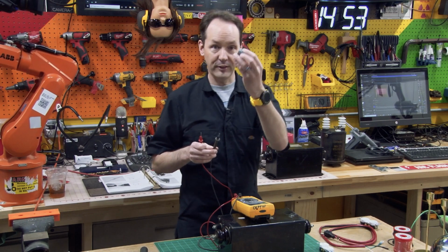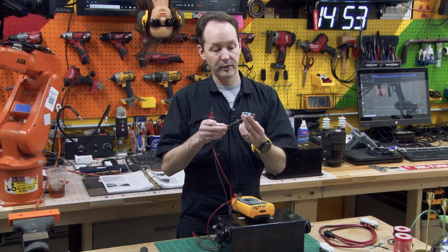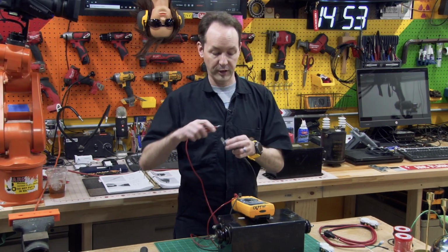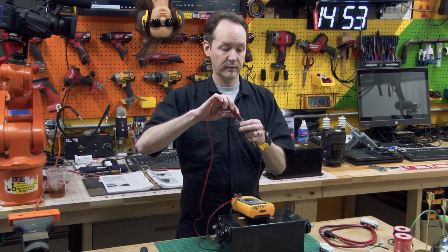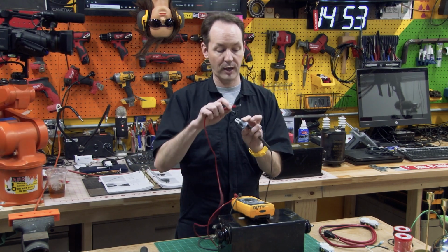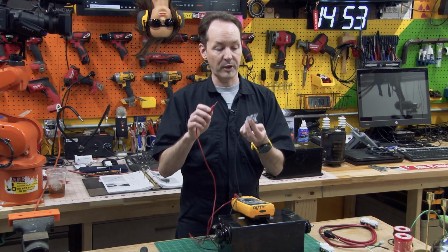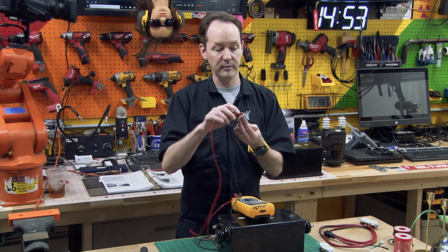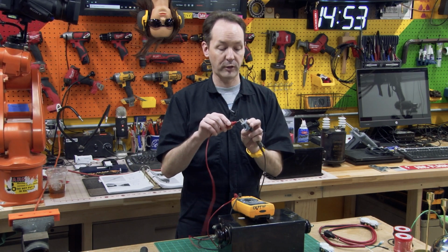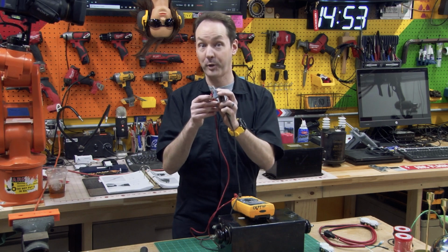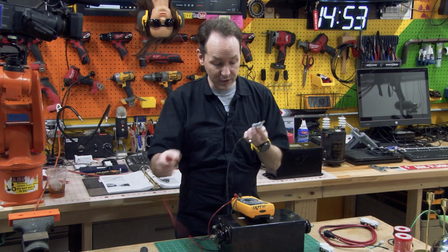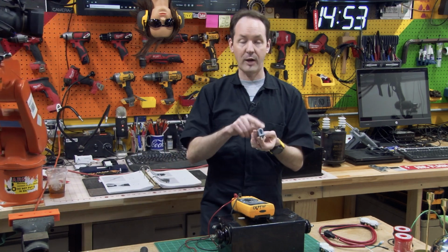Now, if I take this device and put one terminal in there and touch it on the ground thing on the back, it beeps, okay? I'm measuring from ground to the little lug. If I measure from ground to the hot side, nothing. If I measure from ground to the neutral, nothing, and that's the problem, because this doesn't connect ground to neutral.